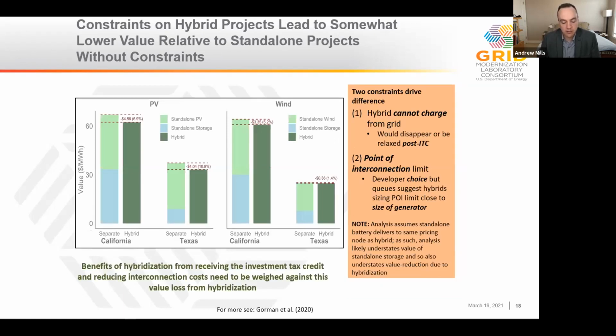Another way to look at this is to compare the value of a standalone renewable generator and standalone battery to the value of the solar or generator and storage integrated into a hybrid plant. The hybrid had a slightly lower value because of two constraints: the hybrid storage could only charge from the renewable generator, and the hybrid had a single point of interconnection with capacity equivalent to the generator capacity. These constraints somewhat lower the value, so you'd need to compare any cost advantages of siting solar and storage together to see if hybridizing's cost advantages outweigh the potential decrease in value from these constraints.